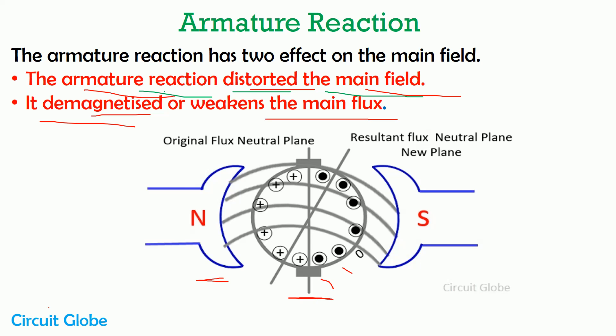In a DC generator, the position of brushes and commutator is decided by the magnetic neutral axis. If the armature reaction weakens the main flux, the position of the magnetic neutral axis will be shifted. So it is quite difficult to know the exact position of the magnetic neutral axis, and if we place the brush in any other position, the brush will get damaged. The armature reaction weakens the main flux, causing the magnetic neutral axis position to shift.